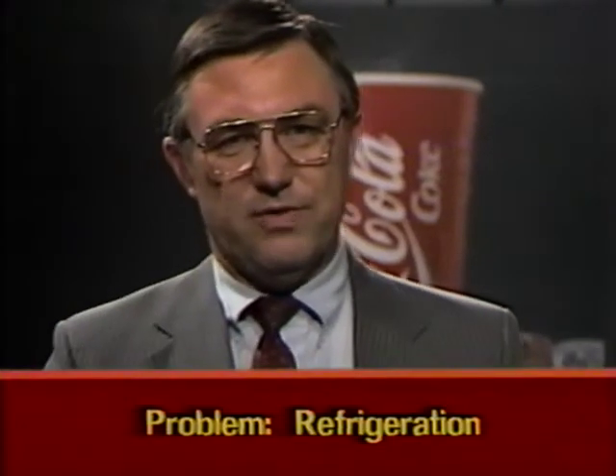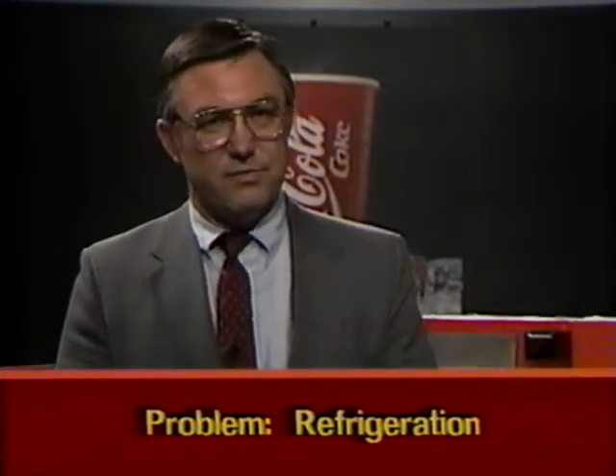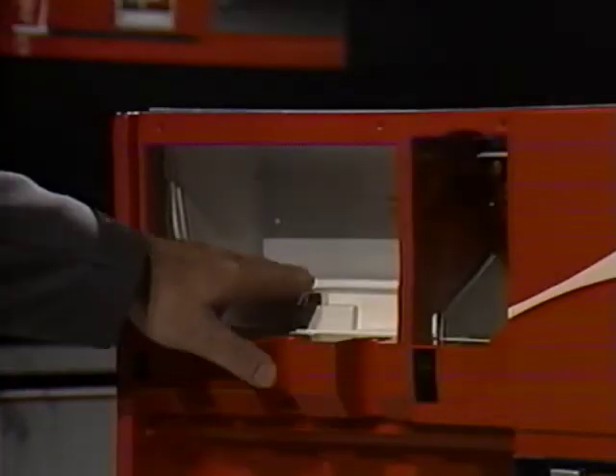Now let's give our attention to the refrigeration system. The BreakMate has a fairly standard refrigeration system, with maybe the exception of the split evaporator system and diverter valve, which directs the freon to the carbonator or syrup cooling compartment as called for by the sensors. Upon immediate startup, the condenser should begin to get warm. The syrup compartment should not get cold for an hour and a half to 2 hours, because priority is given to the carbonator for building the ice bank. This you can feel. After the syrup compartment begins to get cold, you should be able to look in the diagnostic mode and see the normal ice bank light off and the super ice bank light on. And these are good checks you can make before installation to be sure you have proper ice bank.